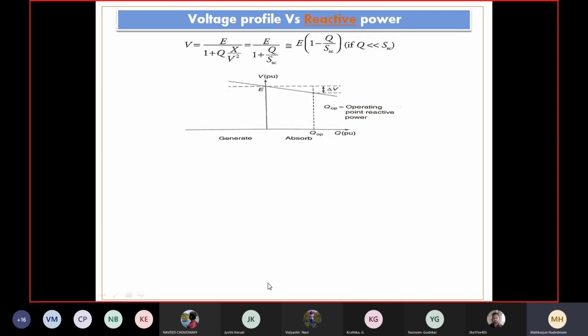Later, if we extend, what voltage prevails? Suppose you have a generator absorbing reactive power and delivering reactive power. What is that mismatch? What is its impact on that generator? We can see from this curve. The generator, with voltage on the vertical axis at the centre, and its reactive power capabilities, generation and absorption, and a slope of its operation we can see. Whenever there is an absorption of reactive power, there will be a dip in voltage.